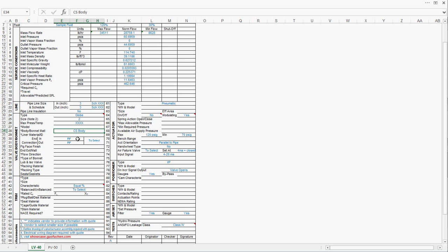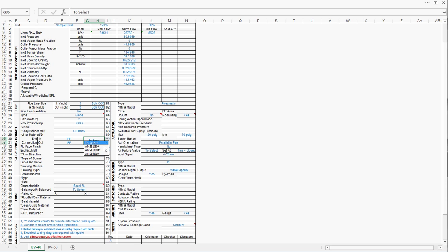Connection between pipe and valves: Generally, flanges are preferred and raised face flanges are most likely used. Since we are specifying flange, flange rating is pretty important. We are talking about 60 psi and 115 Fahrenheit, so ANSI 150 pounds should be sufficient.